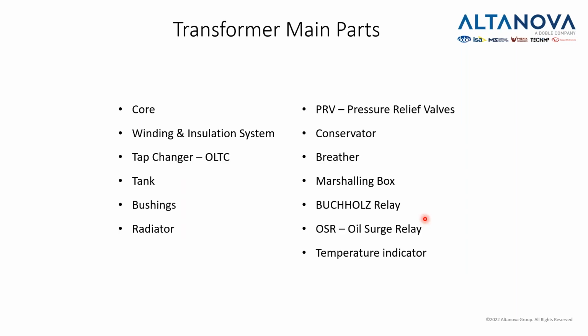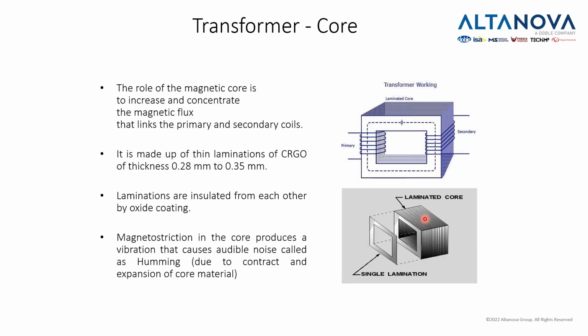What are the transformers' main parts? Core, winding and insulation system, tap changer or on-load tap changer or OLTC, a tank where everything is contained, bushings, radiator, pressure relief valves, conservator, breather, marshalling box, Buchholz relay, oil surge relay, and temperature indicator. There might be some others, but these are the main and the principal ones. So transformer core, let's start with the first one.